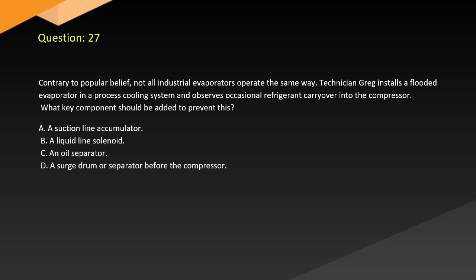Question 27. Contrary to popular belief, not all industrial evaporators operate the same way. Technician Greg installs a flooded evaporator in a process cooling system and observes occasional refrigerant carryover into the compressor. What key component should be added to prevent this? A. A suction line accumulator. B. A liquid line solenoid. C. An oil separator. D. A surge drum or separator before the compressor.